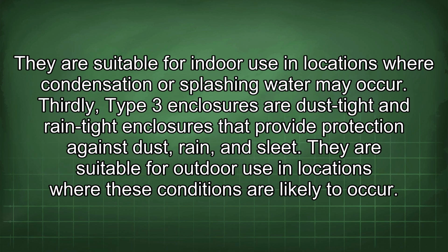They are suitable for indoor use in locations where condensation or splashing water may occur. Thirdly, Type 3 enclosures are dust-tight and rain-tight enclosures that provide protection against dust, rain, and sleet. They are suitable for outdoor use in locations where these conditions are likely to occur.